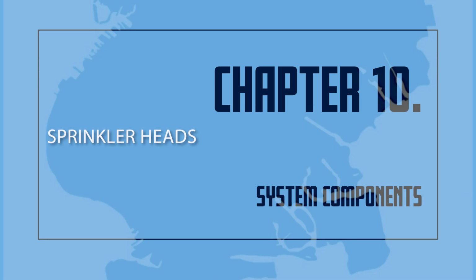The sprinkler head is factory tested to withstand at least 400 psi without injury or leakage. If properly installed, there is little danger of the sprinkler operating unless it is damaged. There are over 50,000 different variations of sprinkler heads. Sprinklers manufactured after January 1, 2000 are required to have an SIN, or Sprinkler Identification Number. Sprinkler heads manufactured prior shall be replaced as required with sprinkler heads of similar characteristics such as orifice size, temperature rating, and deflector orientation.